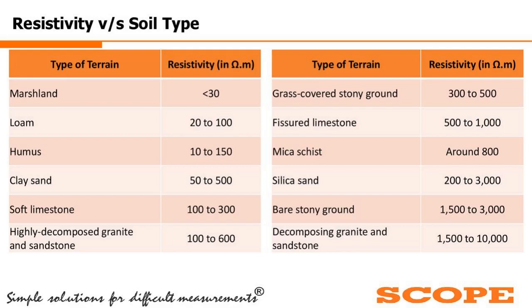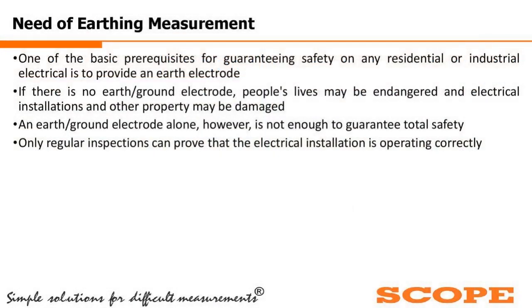And the highest resistivity we can expect is where we have granite and sandstone, because their conductivity is very low, where we can get up to 1500 or even up to 10,000, depending upon what type of granite and what type of sandstone, their composition and all those things. So this is the specific need why we require the earthing measurement.